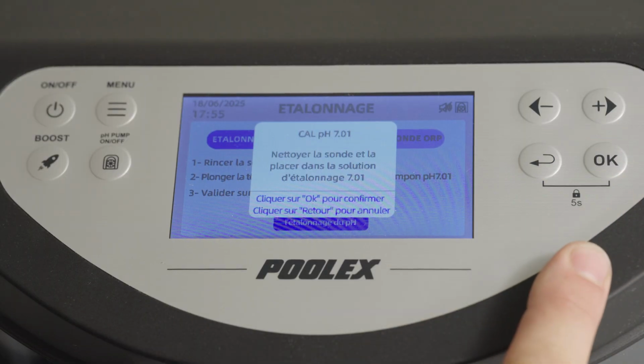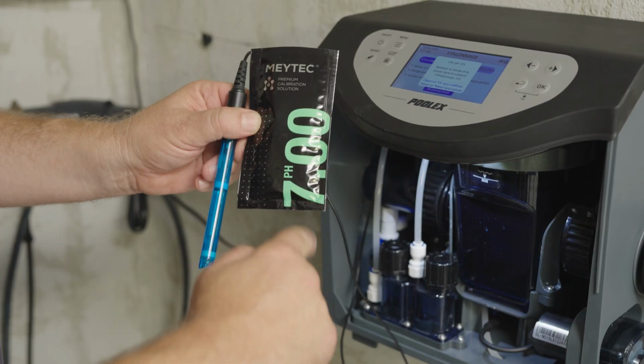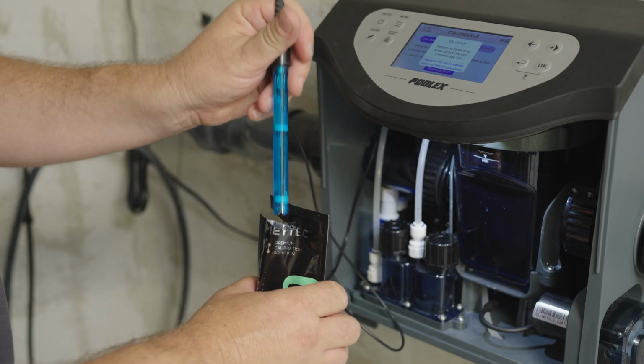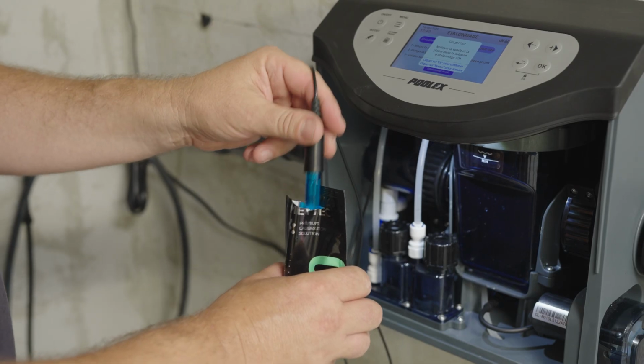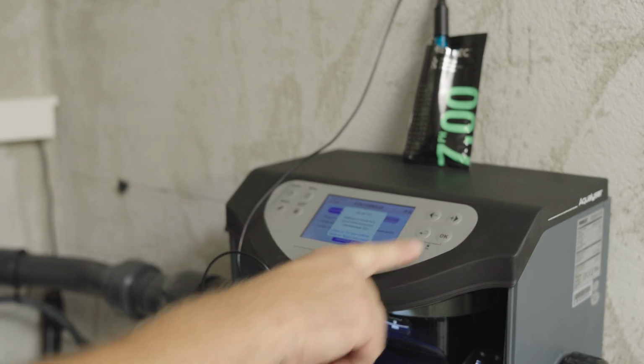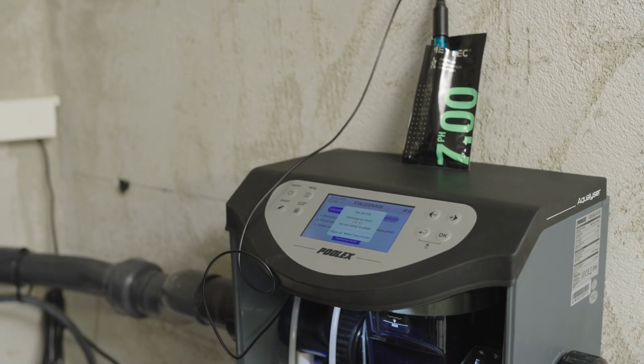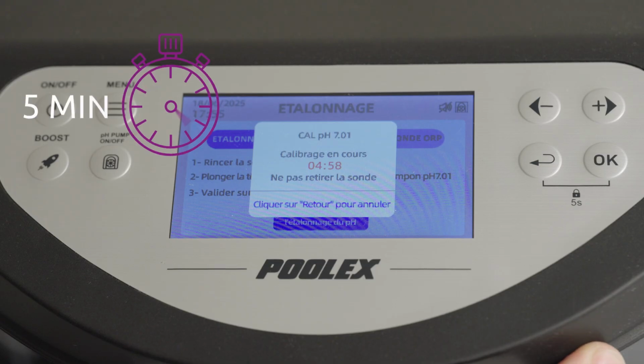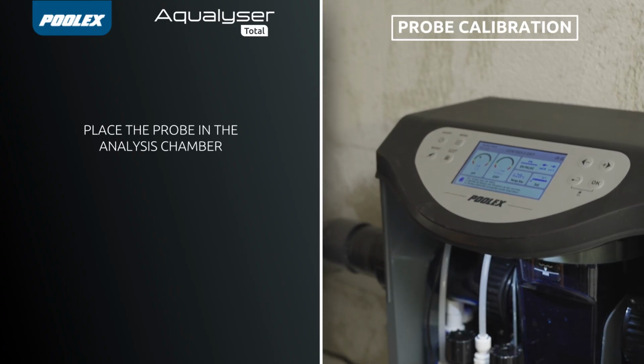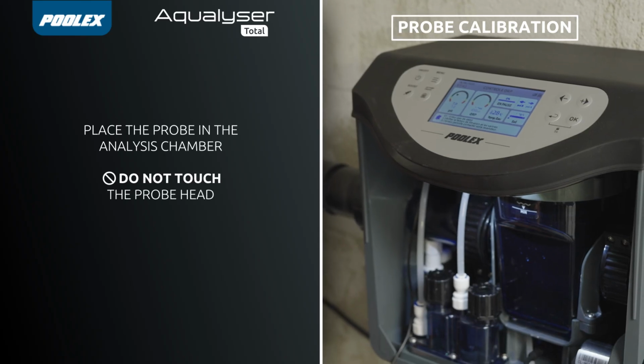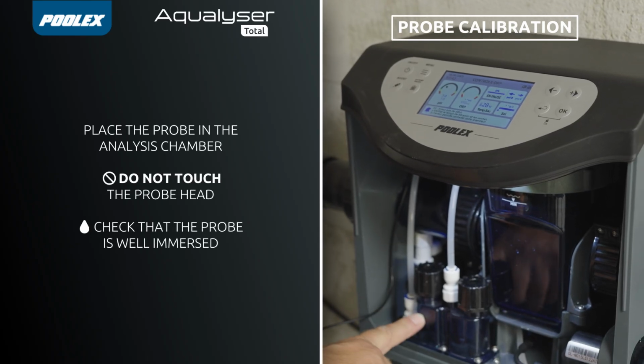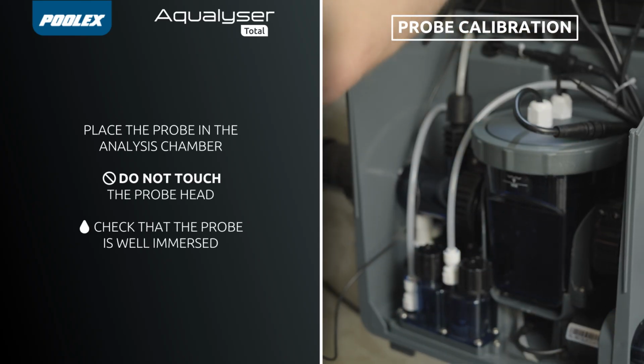A message will guide you to finalize the procedure. Remove the probe from its holder and immerse it in the pH 7 buffer solution. Then press OK. Calibration begins. Leave the probe in the solution for 5 minutes. You can now place the probe into the probe holder of the analysis chamber. Do not touch the probe head with your fingers, and make sure it is properly immersed in water.